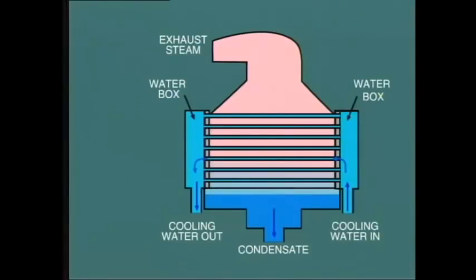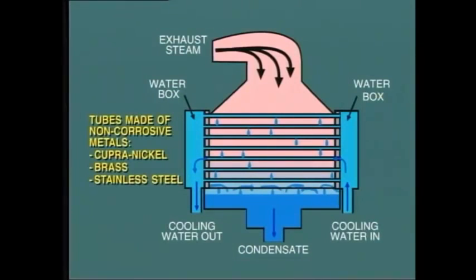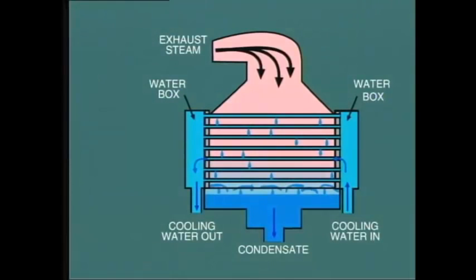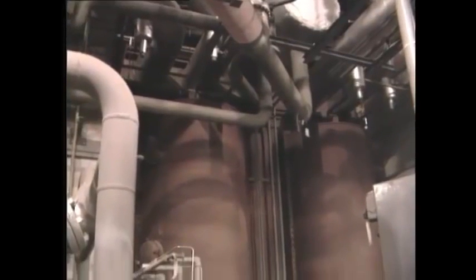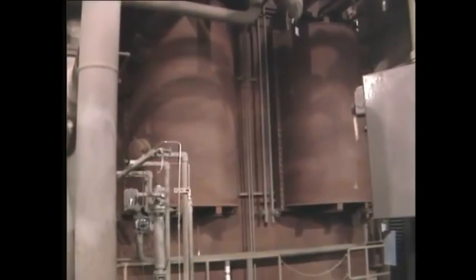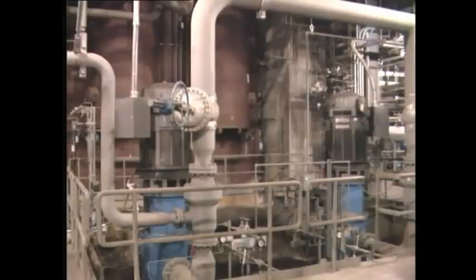The steam space in the condenser is filled with low-pressure steam exhausted from the turbine, which quickly turns to water droplets as it comes into contact with the outside surface of the cooling tubes. Most condensers contain several thousand tubes about 1 inch in diameter, usually made of non-corrosive metals such as copper and nickel, brass, and even stainless steel. Cooling water passes through the inside of these tubes, while steam condenses on the outside of the tubes. This so-called condensate then falls to the bottom of the condenser, where it is collected in a vessel known as the hot well. From here, the condensate is removed by the condensate pump and circulated back to the system.